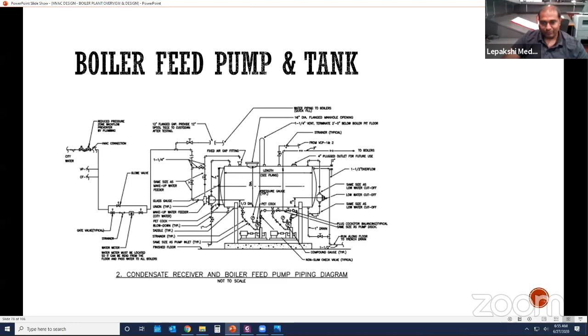Not everything is going to waste, but at the same time, whatever you are losing is coming back to the system from the outside water. That's what it is. No, you can't just dump the water straight into the boiler. If you do, the water has many components. Who knows what's in there, like calcium, nitrates, this and that. So you've got to remove all that stuff. It's going to corrode the boiler material. Boilers are pretty much made of steel, and they get corroded too. So you have to treat the water that's being dumped into the system.